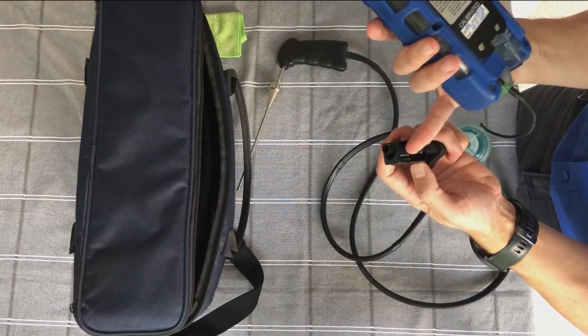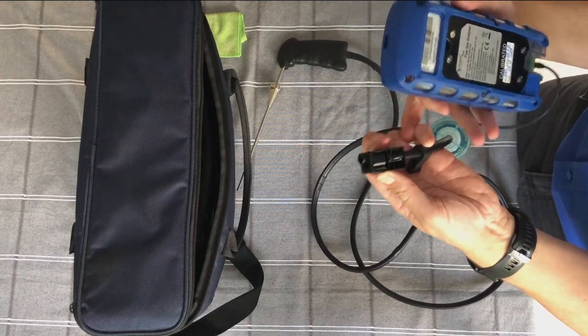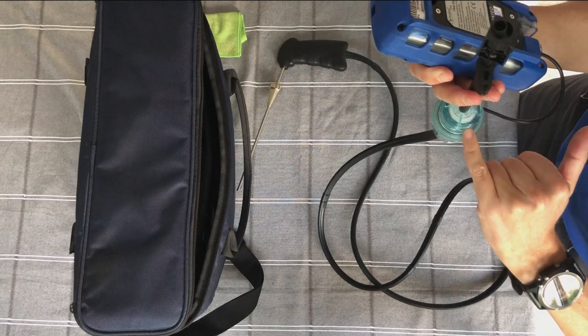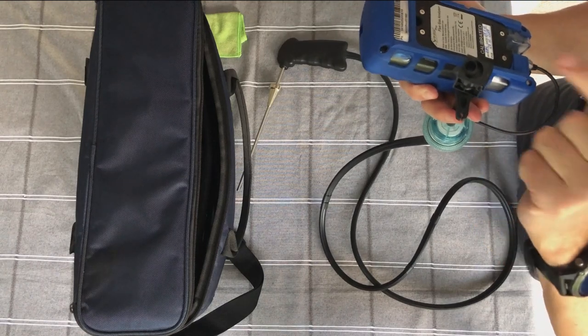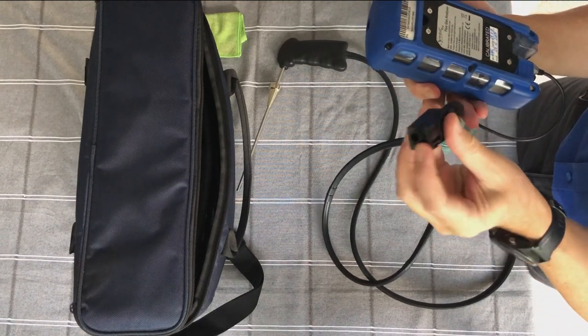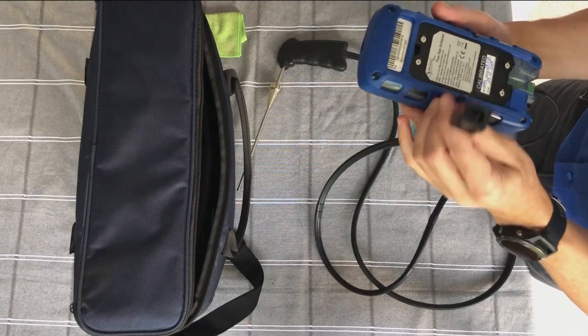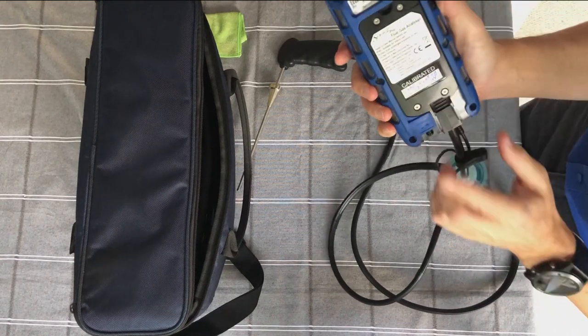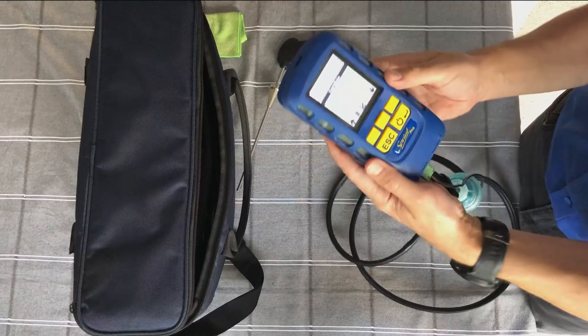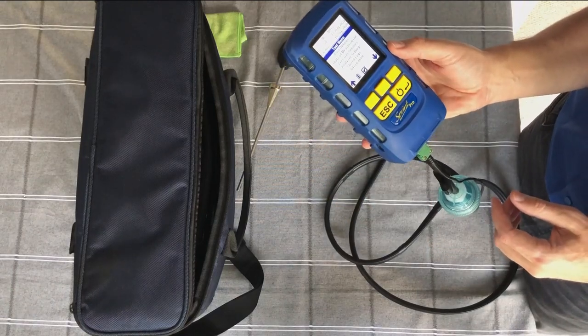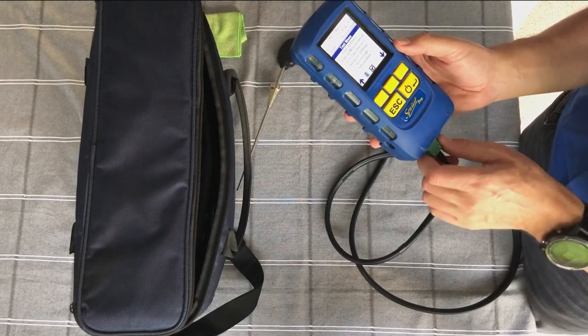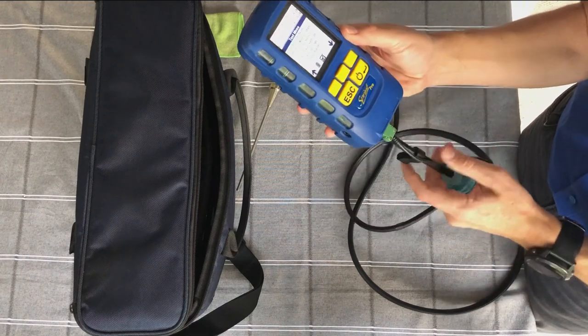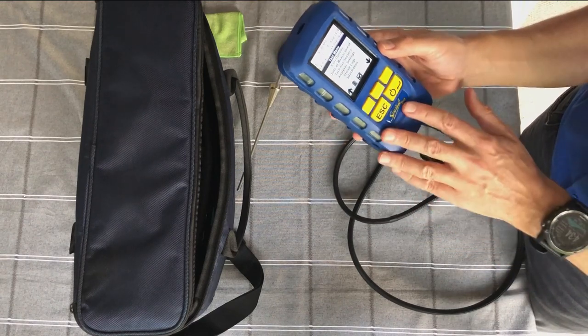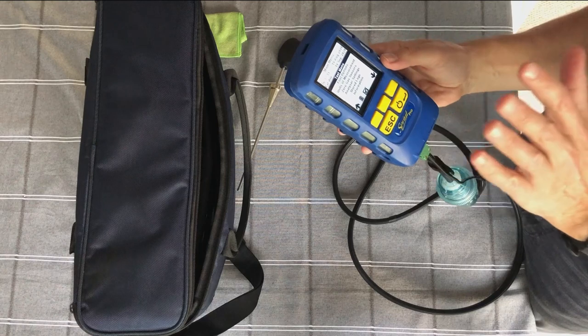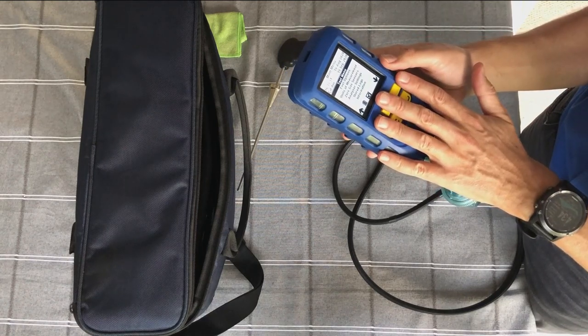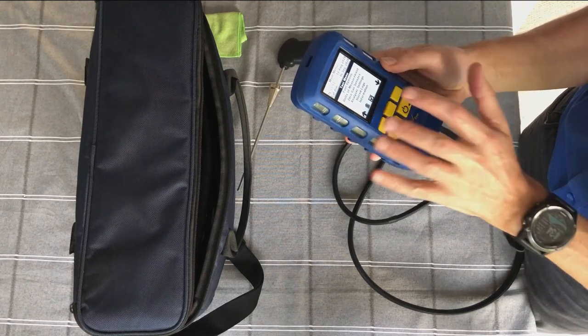Just so you know, there's another one of those hydrophobic filters in the end of this. So whilst that should always be there, because that's easily swappable, worst case scenario, we've got a second line of defense in here that you can't obviously connect into the instrument without that connection. So you're always protected against water damage and moisture damage, which is really, really important. So yeah, once you're up and connected, then you can start the flue gas analysis. So just gonna take a quick breath and we'll come back to that in a second.